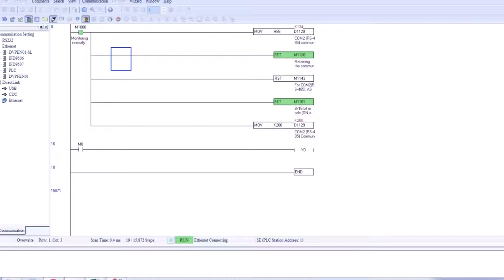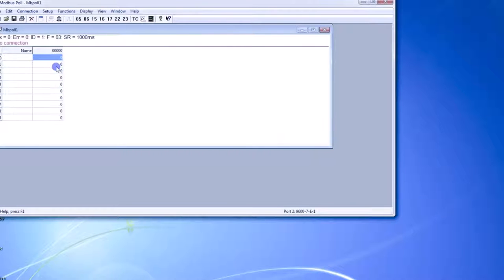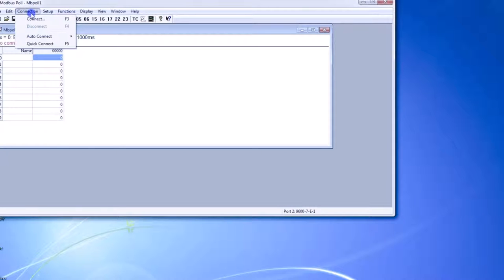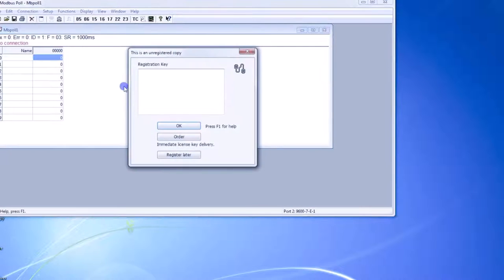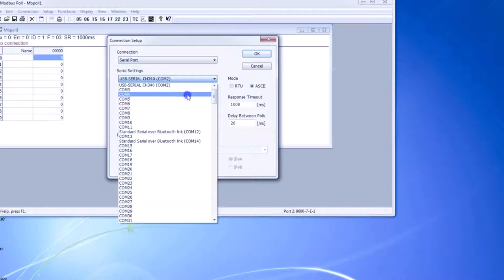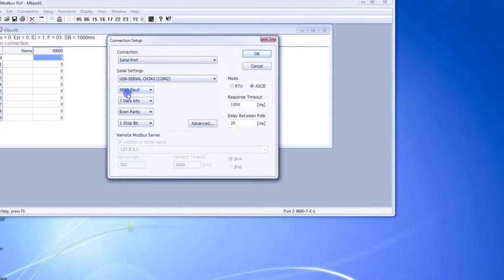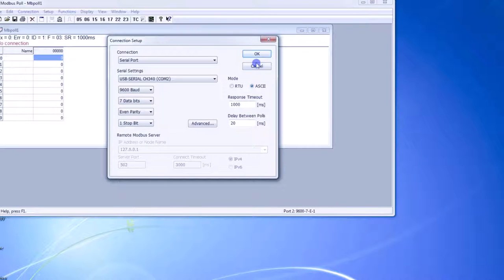Now just open the software which we installed previously — Modbus Poll. You can also use Modscan or any other simulator; I prefer this Modbus Poll which we recently downloaded. Go to Connection and click Connect. We are connected through serial port, so select Serial Port. Here you can select the COM port — we have COM2 so COM2 is selected. Settings: 9600 baud rate, 7 data bits, even parity, 1 stop bit, ASCII mode. Response timeout 1000ms.